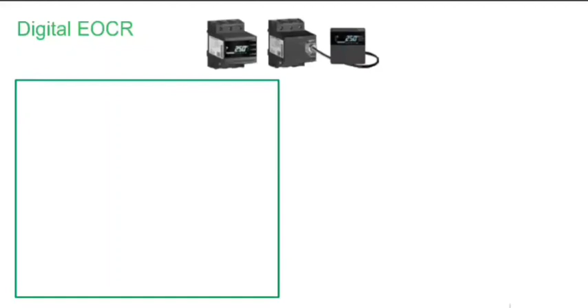For example, if my motor is continuously tripping on ground fault, then basically I need to check my earthing. If there is a problem in phase, it is continuously tripping on phase unbalance, then I can check my electrical system network, I can check the continuity of it. So all these decisions can be taken accordingly. There is a reset option available also, whether it is an automatic reset or manual reset, you can assign that. This product can also be used for low frequency operation. So generally what happens in a multi-motor schematic, when there is a VFD and a customer wants to operate multiple motors at the output of a VFD, then generally each motor will have a different frequency, a different speed also to work upon.